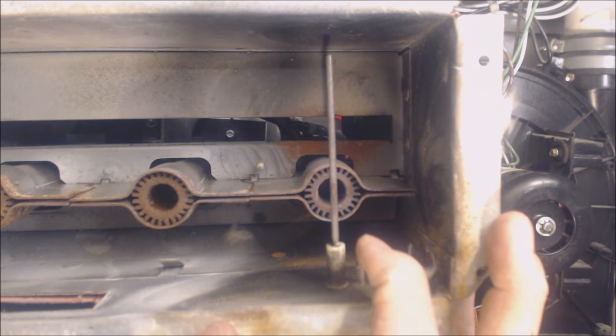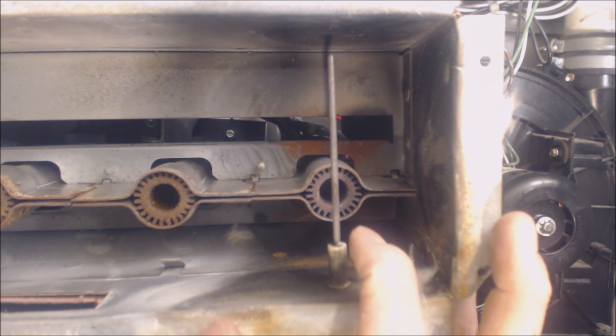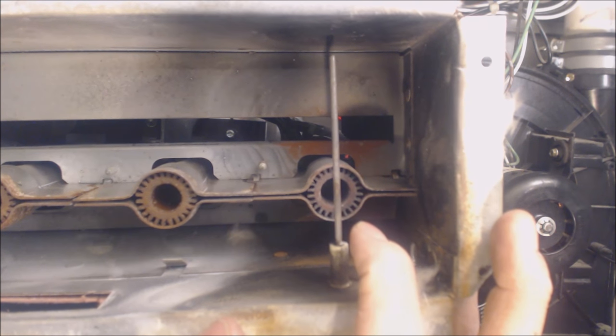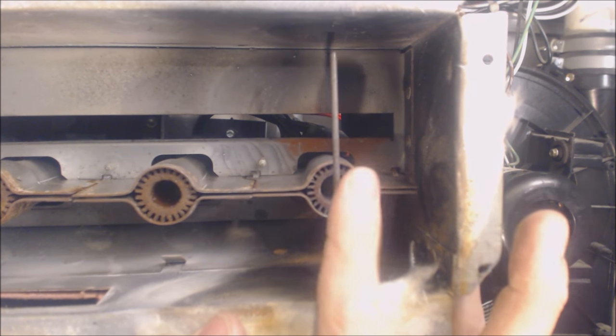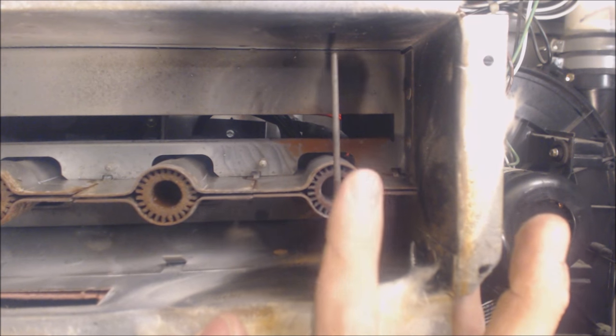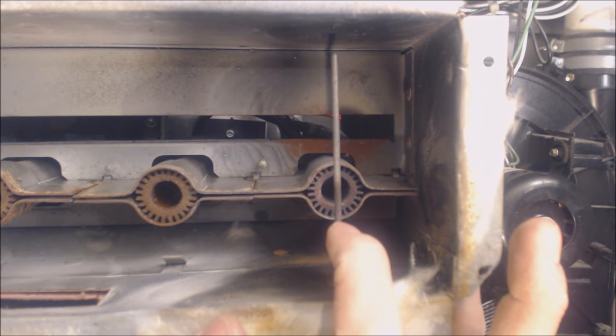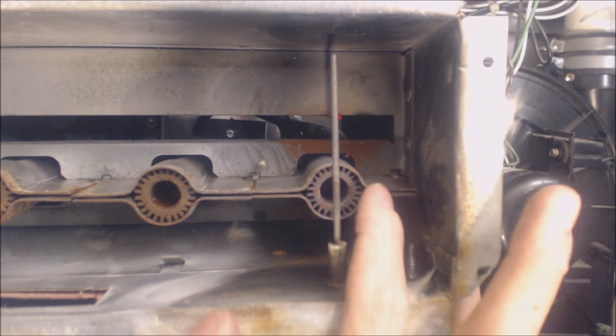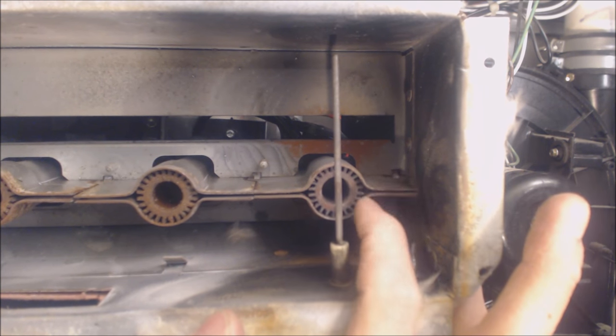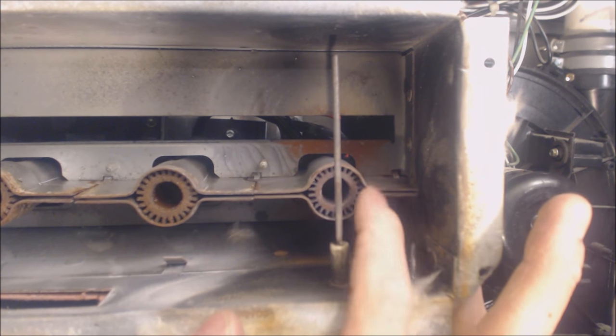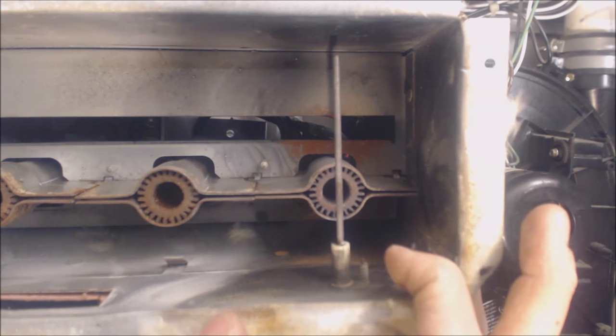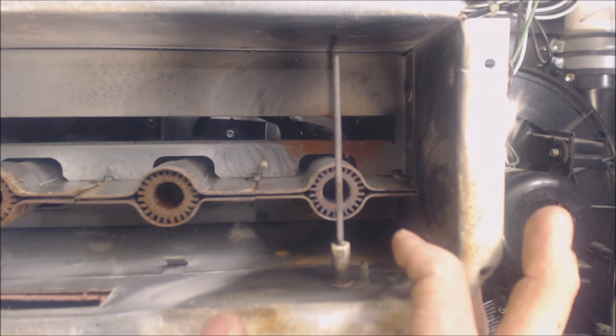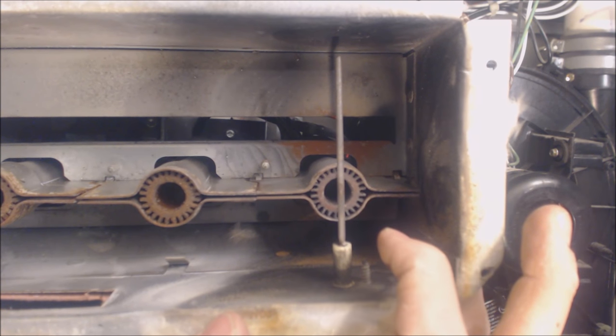And if you're looking at a pilot flame rectification process, a lot of times this rod is a lot smaller because the ground that the flame is touching is smaller. So they're still trying to keep that five to one ratio.